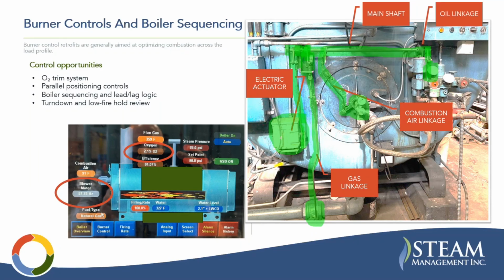Modern systems have, especially an O2 trim system, which I think is very applicable for an industrial setting because you're usually going to have a larger boiler and you're going to be able to justify this. Basically you're going to read an O2 reading in the stack. You're going to have parallel controls of fuel and air, and you're going to modulate those to optimize combustion. In this case, they have a VFD on the fan as well, so you're going to get some electrical savings from the VFD. But that's the idea.